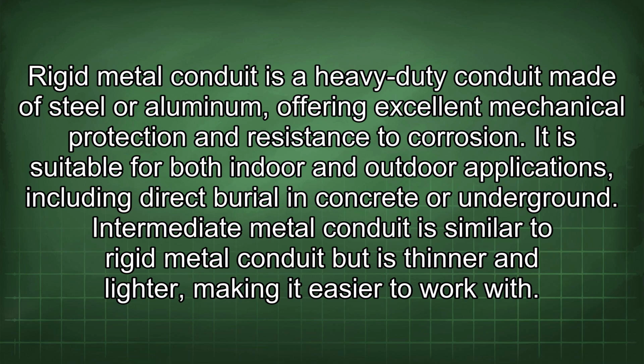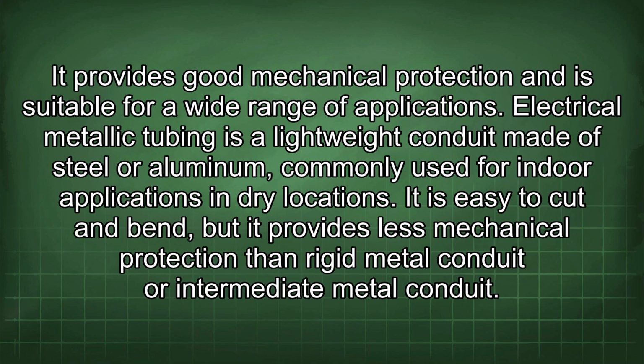Intermediate metal conduit is similar to rigid metal conduit but is thinner and lighter, making it easier to work with. It provides good mechanical protection and is suitable for a wide range of applications. Electrical metallic tubing is a lightweight conduit made of steel or aluminum, commonly used for indoor applications in dry locations.